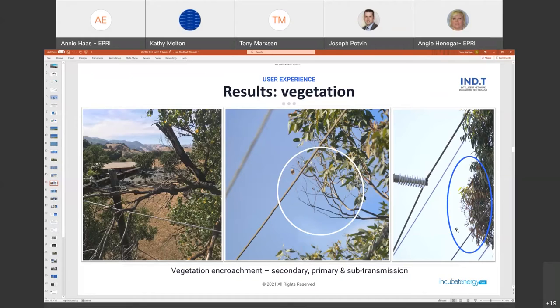In the middle, you've got an example of what we call a pruning fault, where the branch touches a line, dies back, which fixes the problem for a while, then regrows and it goes through the same cycle again. We've also had direct vegetation touches on high voltage, 22 kV in the right-hand photo, and up to 66 kV vegetation actually touching the line. It's something that early fault detection systems pick up with depressing regularity.